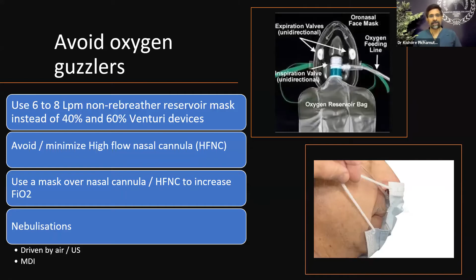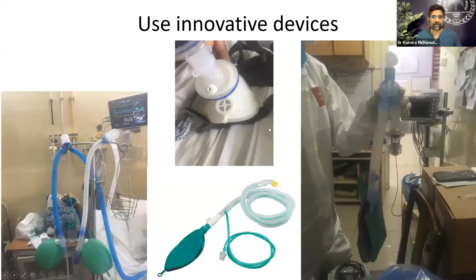Over this second wave, we've heard, in many webinars, people in different parts of the country making different innovations to reduce oxygen use, and these are some of them. This is a simple Bain circuit which provides positive pressure, and in doing so we can reduce the oxygen requirement of patients who are sometimes on 100% oxygen. We've made certain innovations in our hospital using ventilator tubings and reservoir bags that have helped us give positive pressure at very low flows. Like this example here, with a small PEEP valve that's just connected to a mask; it's a low flow mask, and yet it gives us positive pressure, reduces the patient's work of breathing, and reduces oxygen consumption as well. So it's important to keep looking out for what you can innovate with the equipment you have.